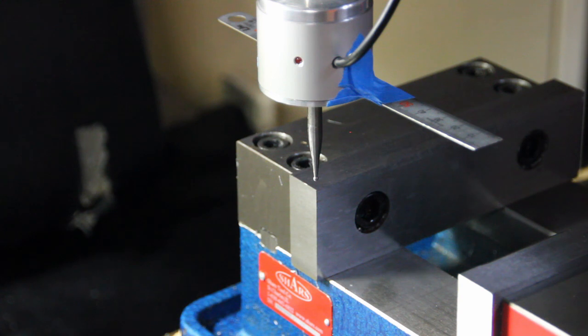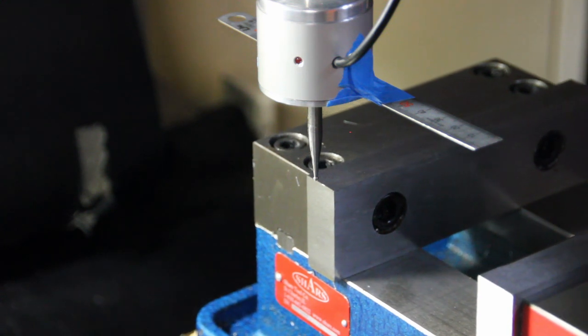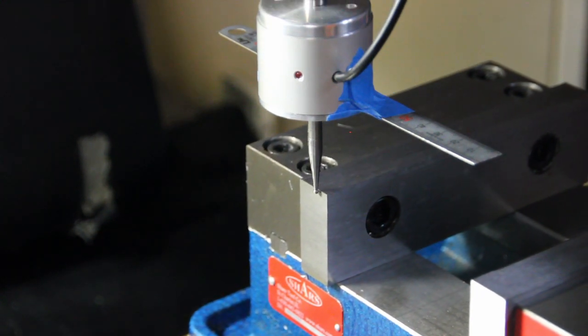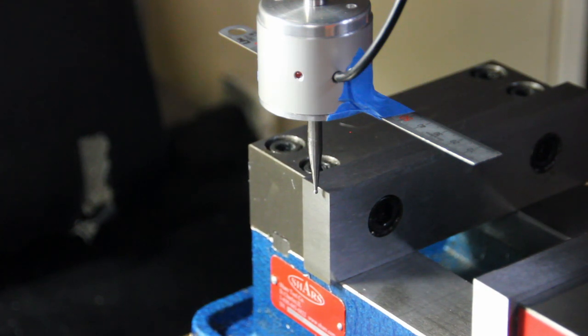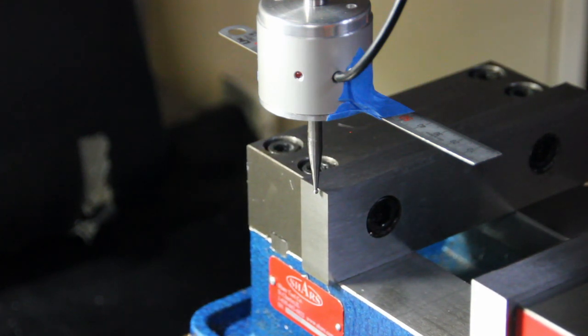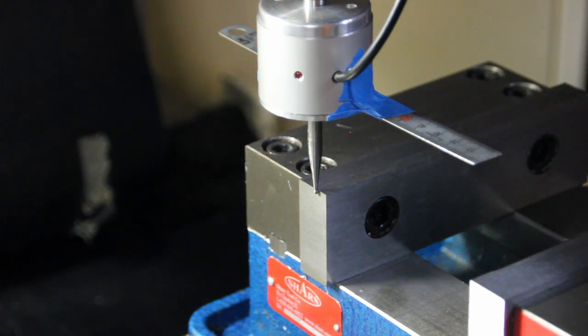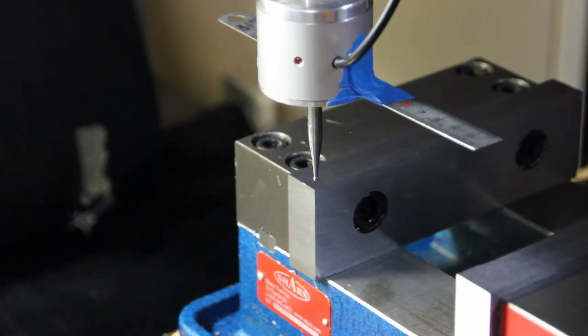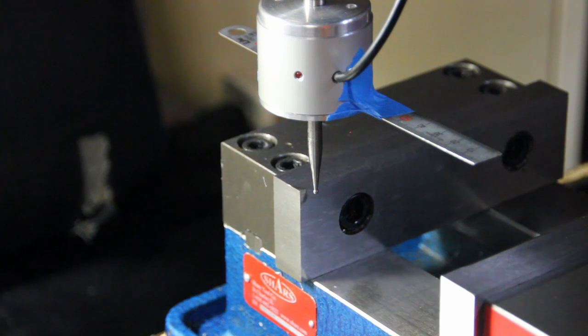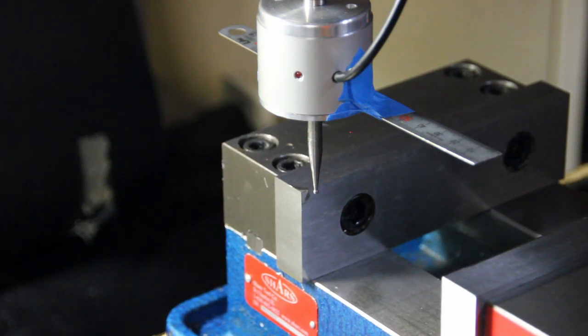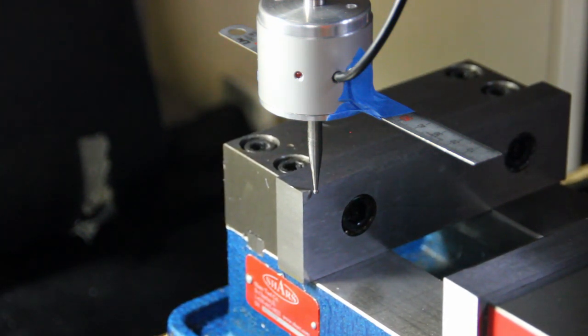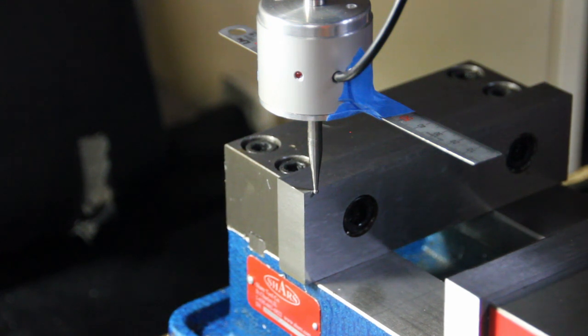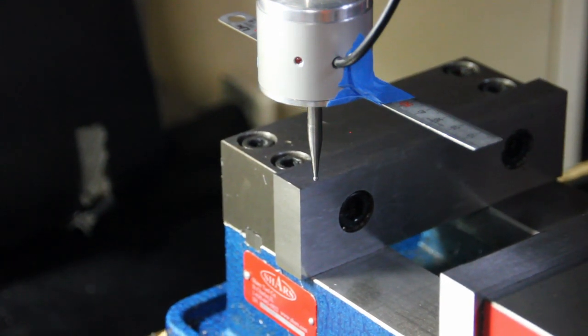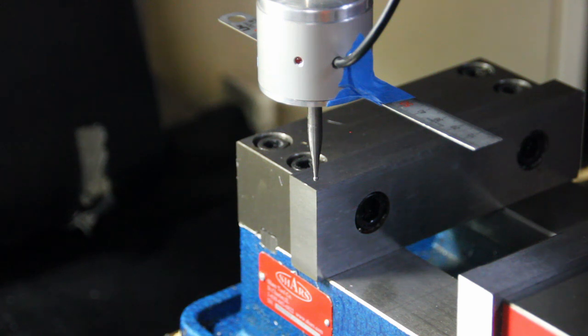And I'm going to leave auto 0 on again, and we're going to do it again. That's better. The good thing is that as long as the machine's not moving so fast that it can't stop, when the machine detects the probe tripping, it will stop movement if it's not expecting it to be tripped in a probe motion. So I can demonstrate that in a minute.